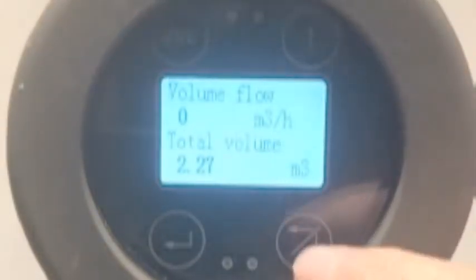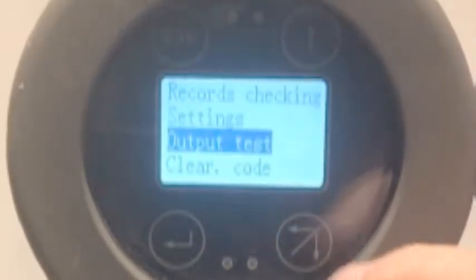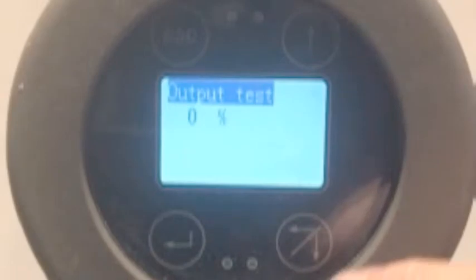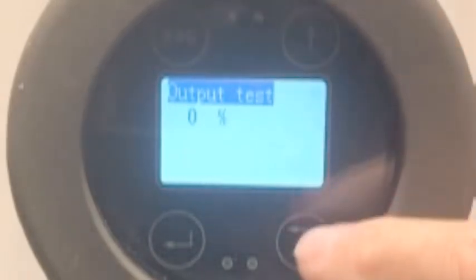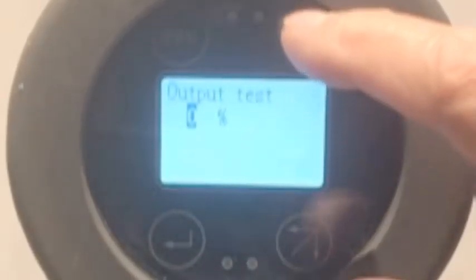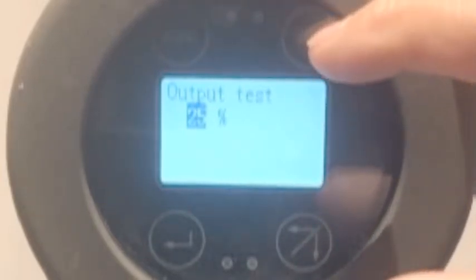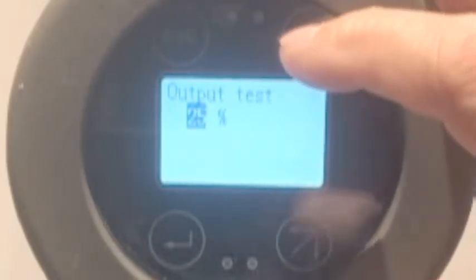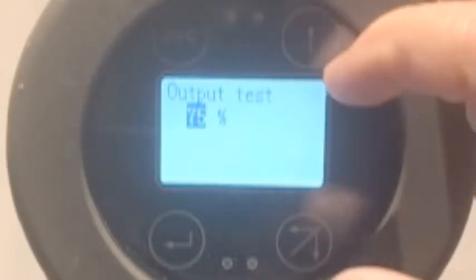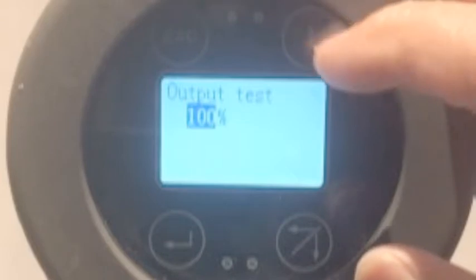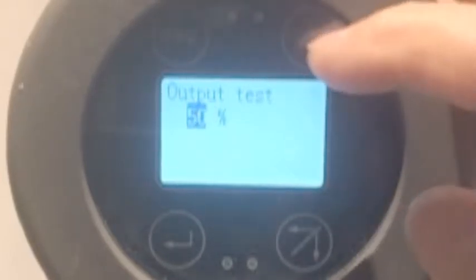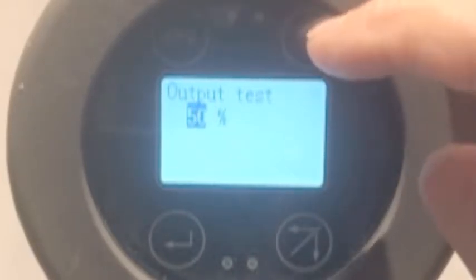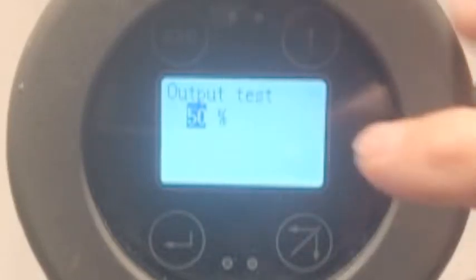I'm going to hit Escape and then Enter, enter the password 2-0, and hit Enter. The output test — I'm going to click Enter. What this does: as I hit the numbers and Enter, it drives the 4-20mA and the frequency output. So this will be at 2,500 hertz, 5,000 hertz, 7,500 hertz, and 10 kilohertz. You'll see that right in the next video where I'll show you the frequency counter.